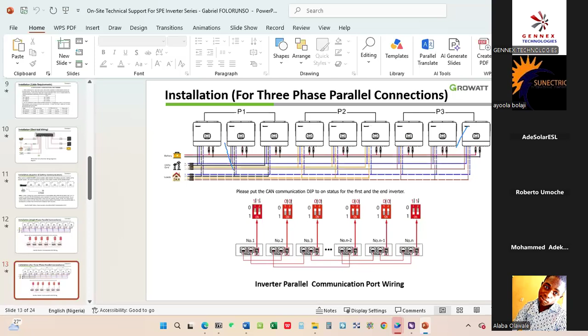Next slide please. This is now how to systematically install the CT onto the inverters. If you look closely at the inverter base, there's a part called EXT, meaning external current transformer. It has a connection there labeled 1, 2, 3, 4. Your attention should be on numbers 1 and 2 - you'll simply put the cables from the CT onto points 1 and 2.